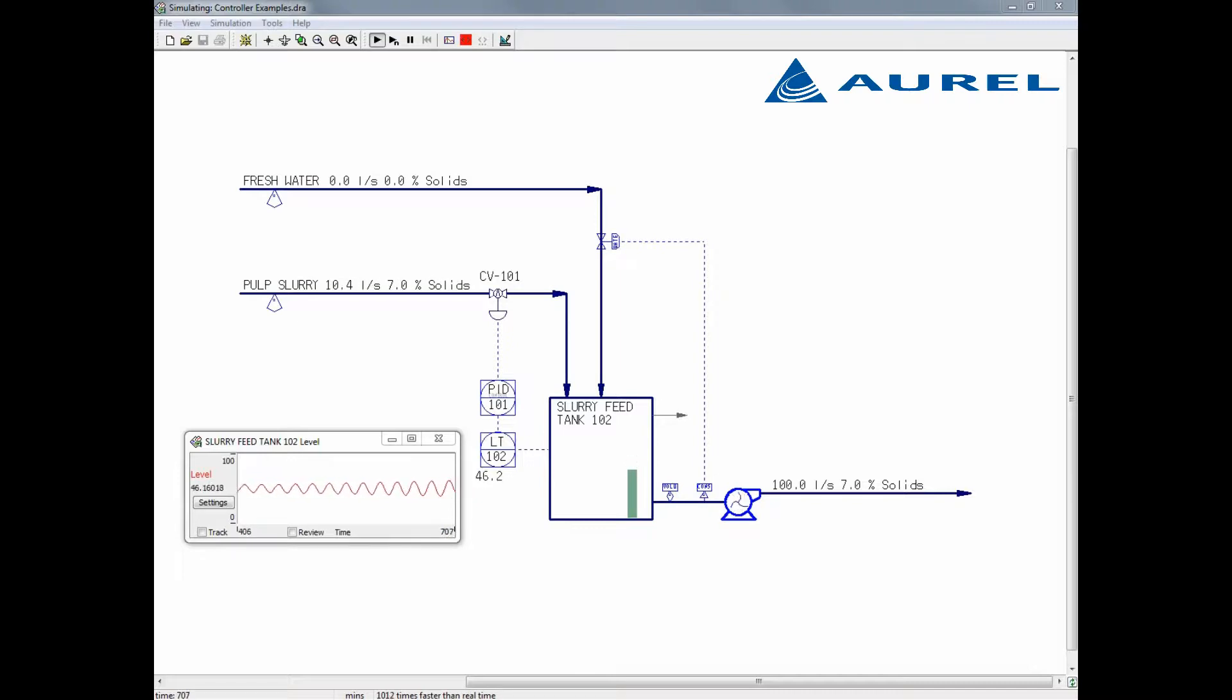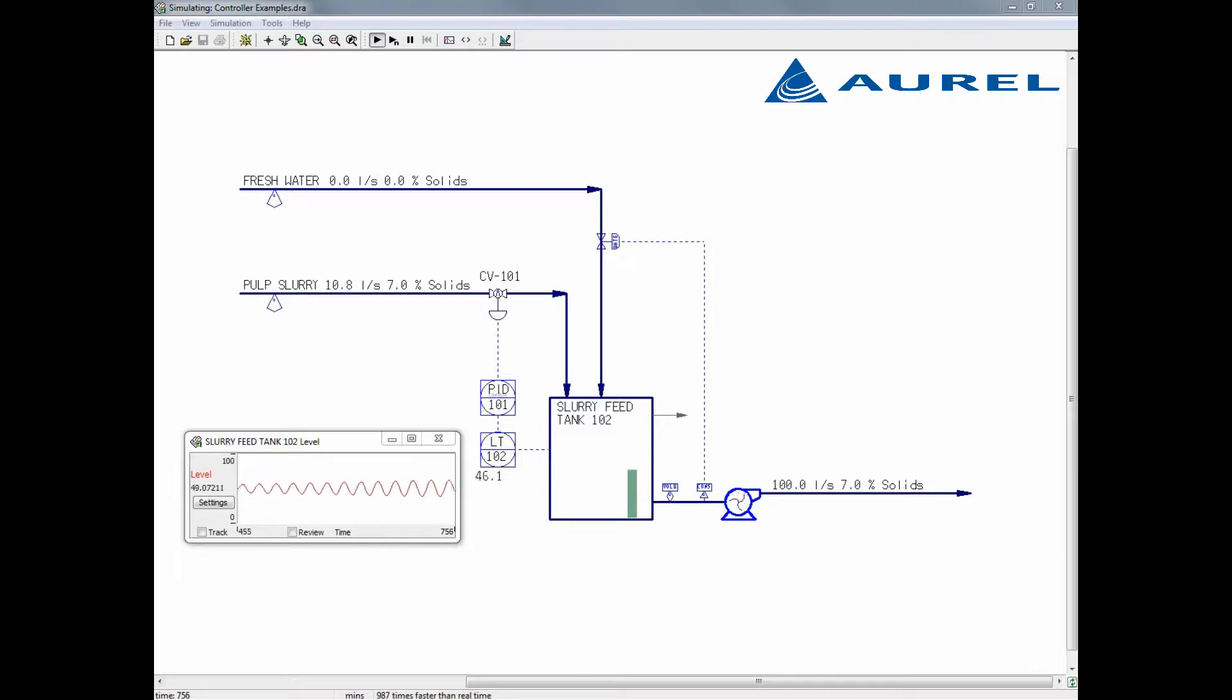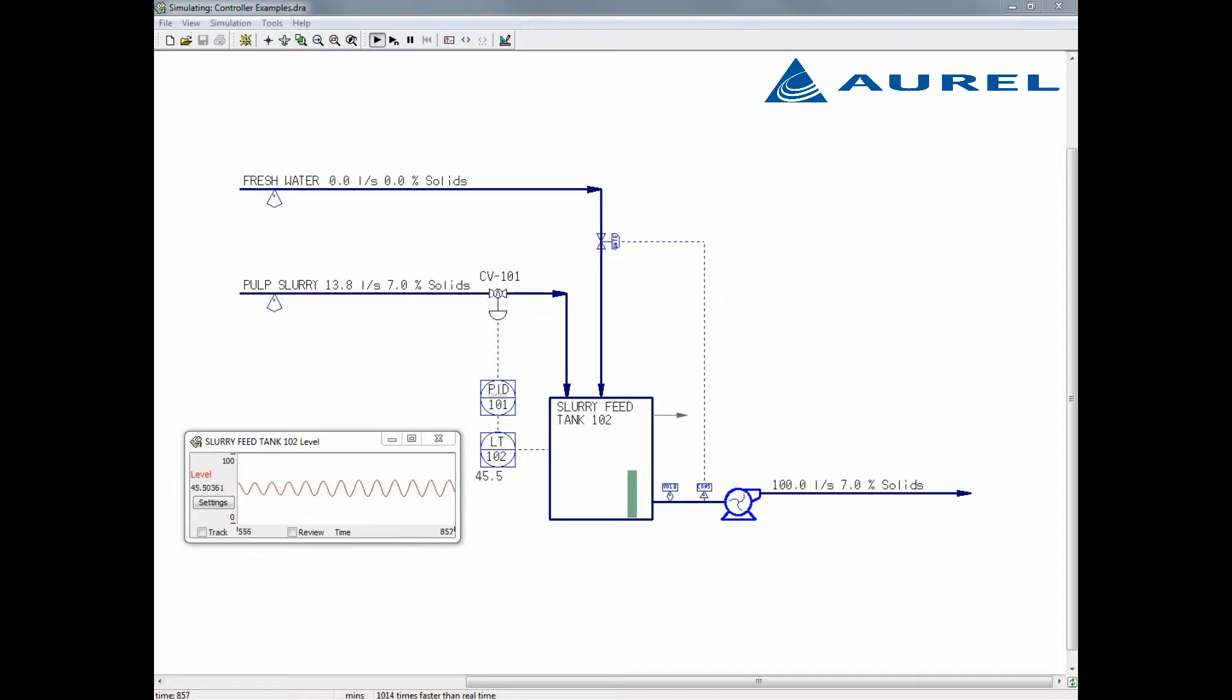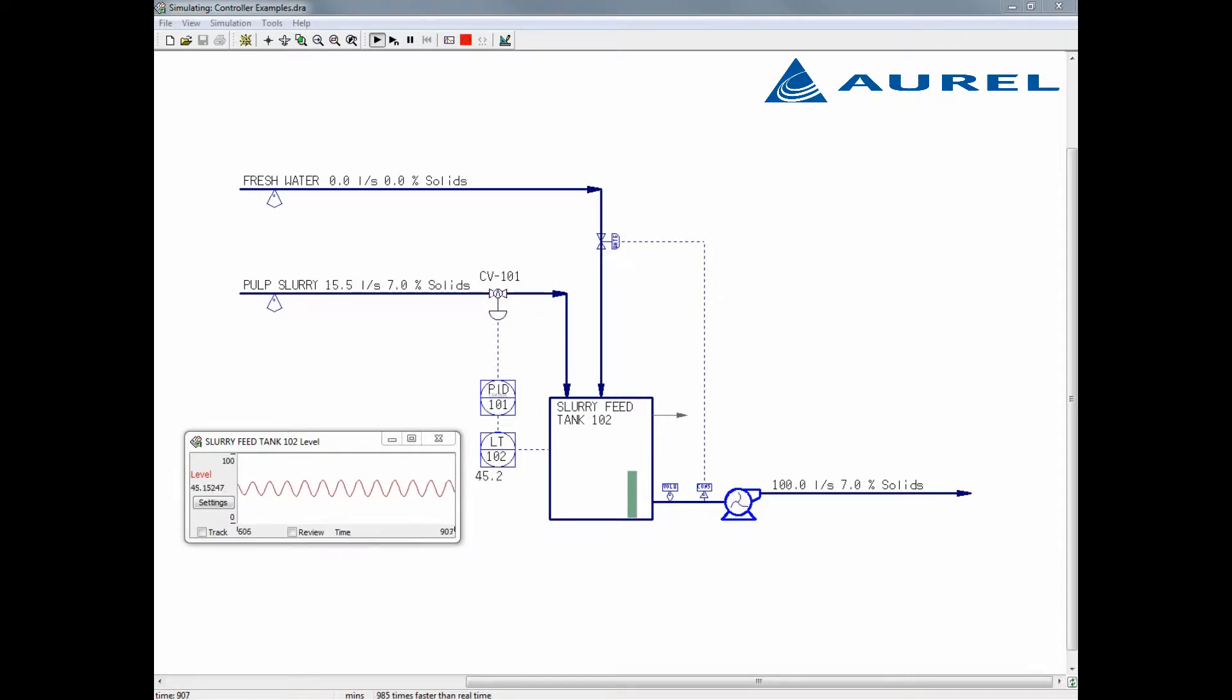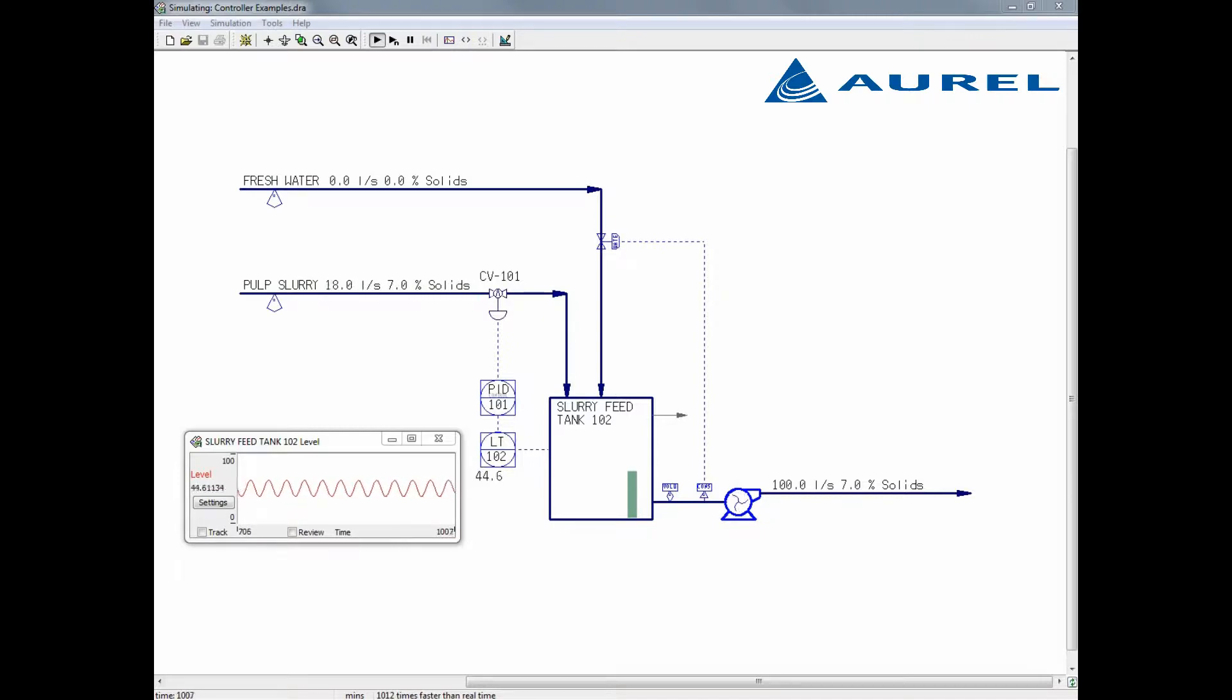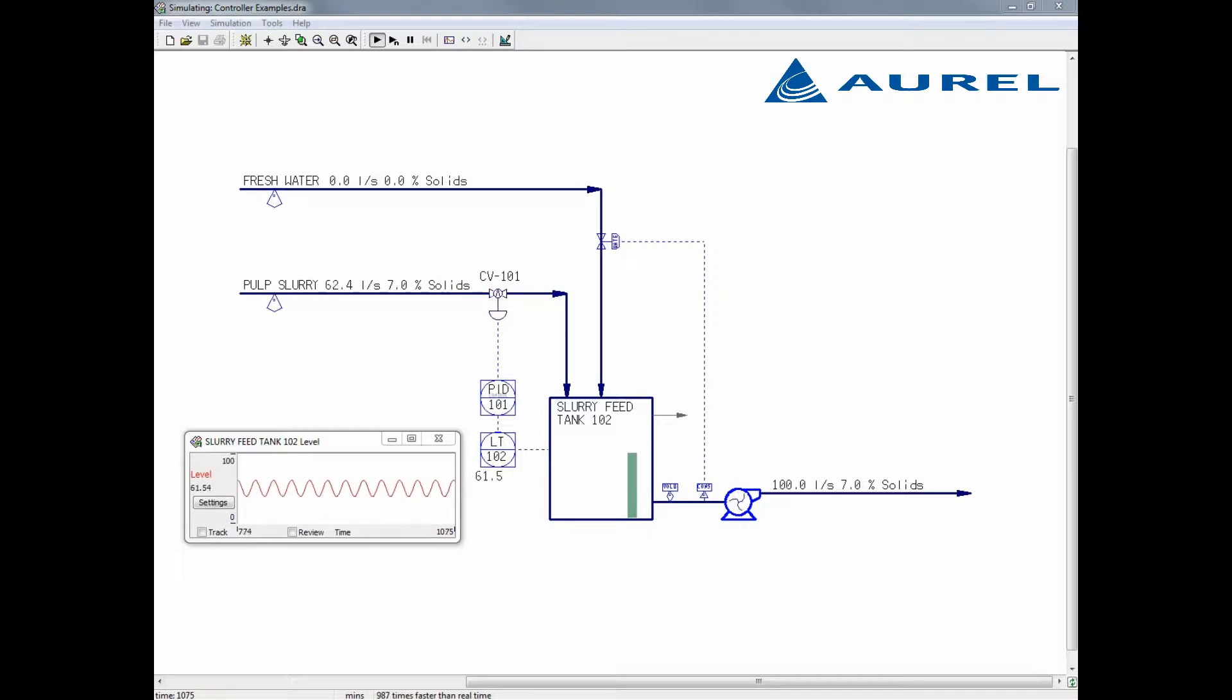Here we can see I have a tank with two streams entering and a single stream leaving the tank. One of the streams entering the tank is a fresh water stream and the other is a pulp slurry with 7% consistency or 7% solids. The flow leaving the tank is a set value of 100 litres per second. The slurry stream will be used to maintain the level at 50% while the fresh water stream will be used to maintain a consistency of 5%.